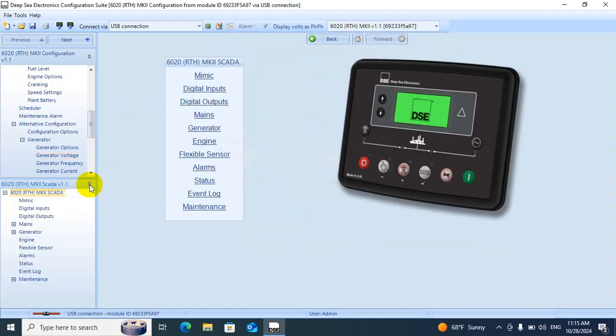SCADA. In SCADA, if there is any change, we are bringing it to the module. No need to load that program back to the module. But in this menu, we have to load it, otherwise it will not save in the module. But here, when we change something, it is direct.